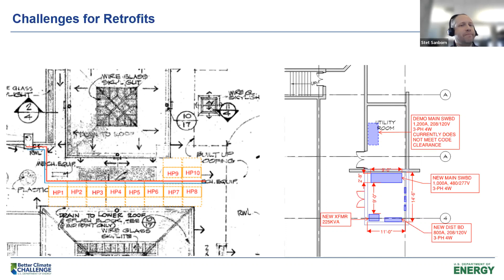I did want to highlight that because this building did not have air conditioning, the electrical service was way undersized to meet this new heat pump load requirement. So we ended up having to upgrade the service, and we couldn't do it lightly, because the existing service for this building was original to the 1960s expansion, and nobody was willing to touch it. So it is going to be getting a full upgrade.